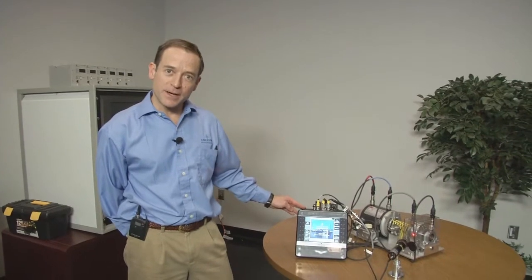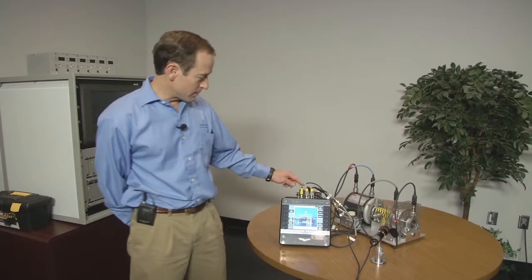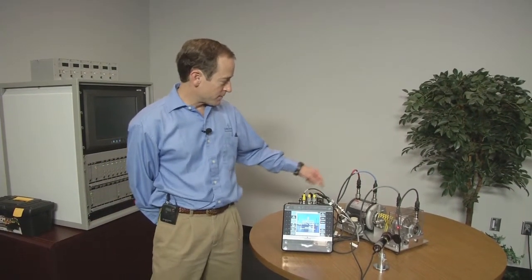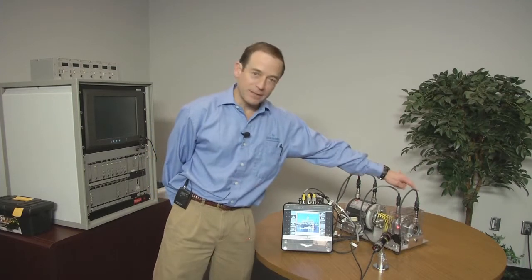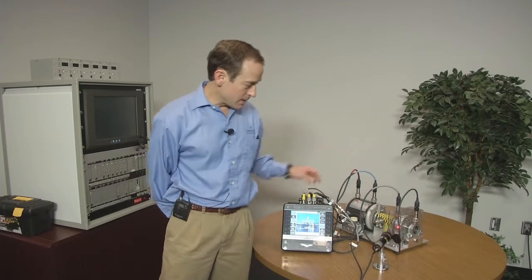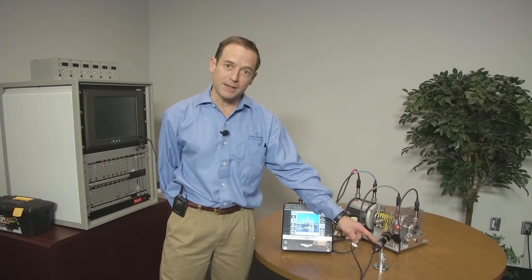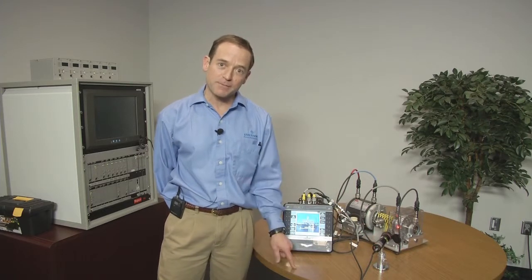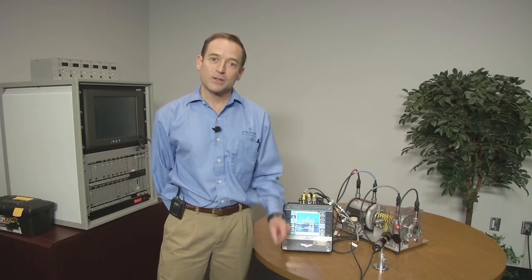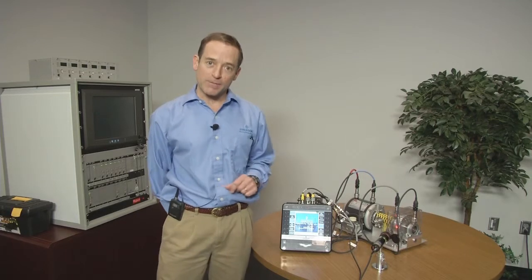What I'm going to be demonstrating is transient analysis using four channels. These are four channels going across the complete machine train, and we're going to be bringing in speed at the same time to capture the speed information with the extended time waveforms.